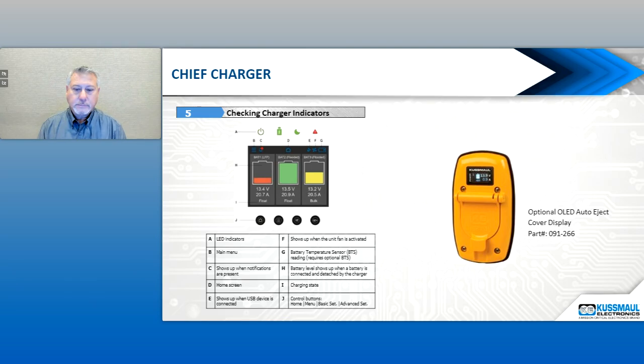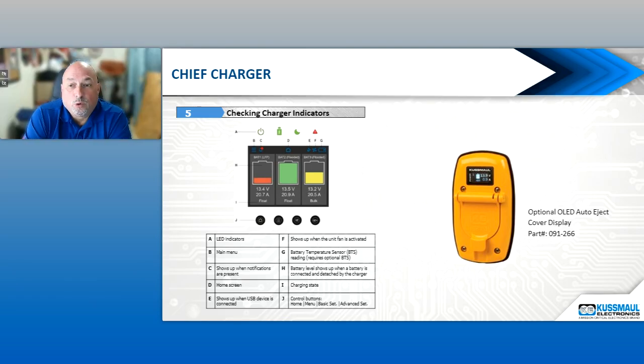The other part about the Chief Charger is its adjustability. Where we had dip switches on the new generation 1200, here it's touchscreen. So you can go in and change the charger from a float charger to a 3-step charger. If you put it in 3-step, remember how the 3-step worked in bulk, absorption, and then float, you can set the absorption to only be 3 hours instead of 9 hours. So it has adjustability that you can do with the charger.